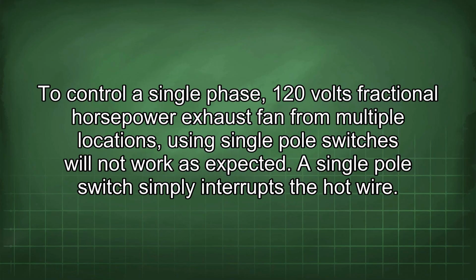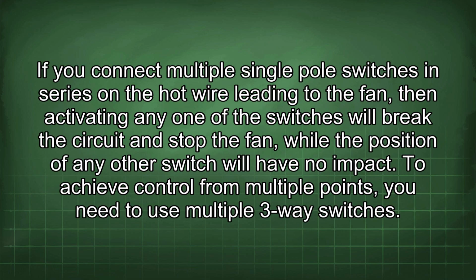Controlling a single-phase, 120 volts fractional horsepower exhaust fan from multiple locations using single-pole switches will not work as expected. A single-pole switch simply interrupts the hot wire. If you connect multiple single-pole switches in series on a hot wire leading to the fan, then activating any one of the switches will break the circuit and stop the fan, while the position of any other switch will have no impact. To achieve control from multiple points, you need to use multiple three-way switches.